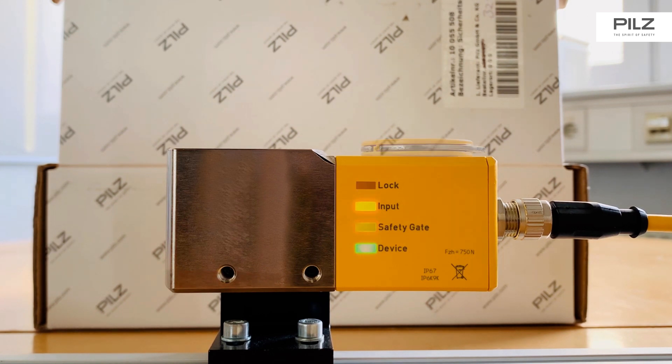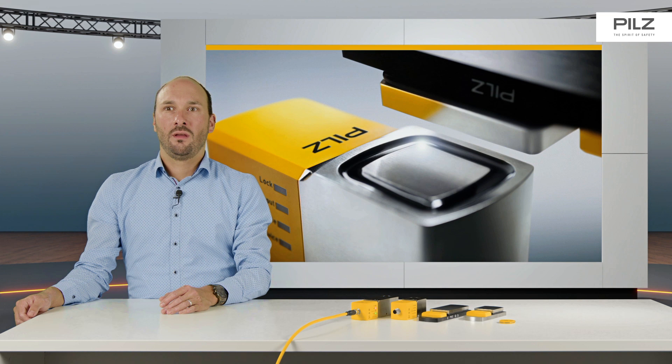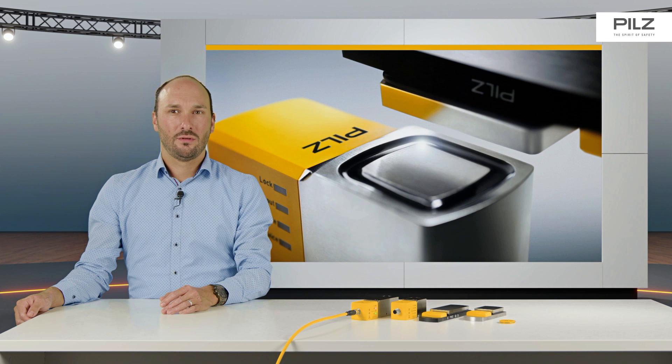The latching force can be set to 30N, 110N, and 200N. The selected latching force can be recognized by the LEDs lighting up. A series connection with SDD enables the retrieval of extended diagnostic data and reduces the wiring effort at the same time.